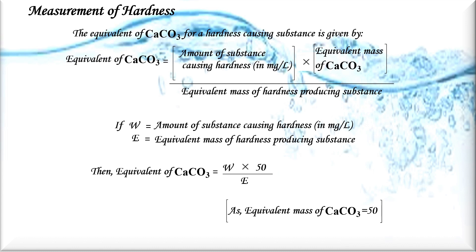To measure hardness, the equivalent of calcium carbonate for a hardness-causing substance is given by: the amount of substance causing hardness in milligrams per liter, multiplied by the equivalent mass of calcium carbonate, divided by the equivalent mass of the hardness-producing substance. So if W equals the amount of substance causing hardness in mg/L and E is the equivalent mass of the hardness-producing substance, then the equivalent of CaCO₃ equals W × 50 / E, since the equivalent mass of calcium carbonate is 50.